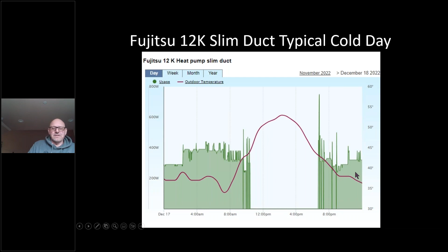Here's another typical cool day in December, last December. This equipment is just running at 35 degrees out, not even on high stage. This is probably first or second stage. I don't know how many stages it has, probably 10 or 12. Then all of a sudden the sun comes out and it doesn't need any heat. Around 7 or 8 o'clock in the afternoon, it comes on again. Just these long run cycles, beautiful, long, efficient run cycles with very low consumption of watts.